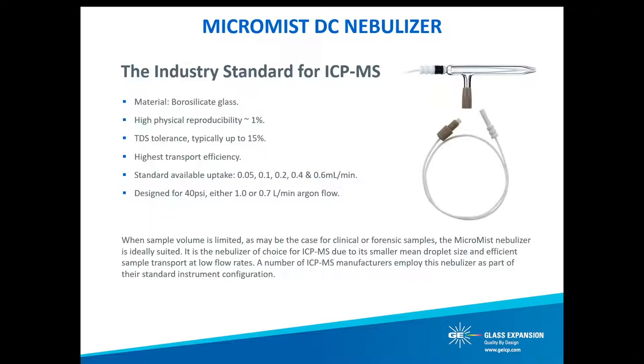This means the MicroMist nebulizer can reduce sample consumption by a factor of 40, yet sensitivity is only reduced by less than a factor of 2. Common applications where the MicroMist performs well include applications requiring the highest sensitivity and precision such as toxic metals in cannabis, ICP-MS applications where oxide interferences exist, samples with limited volume such as those difficult to digest or biological samples, radioactive samples where minimum waste is desired, and volatile organic solvents that would otherwise cause an excessive load or extinguish the plasma.